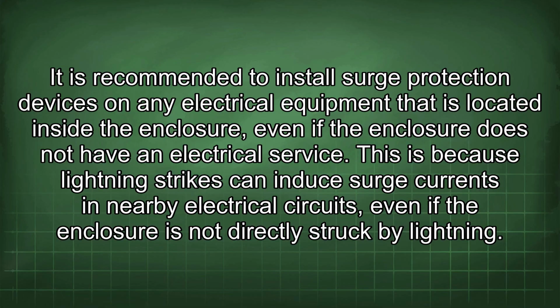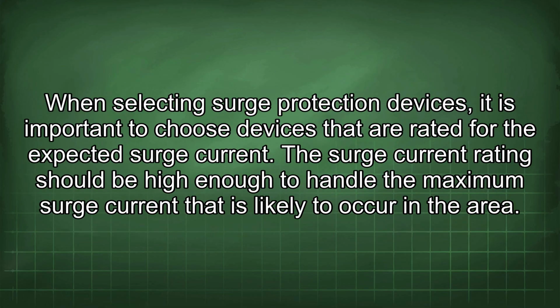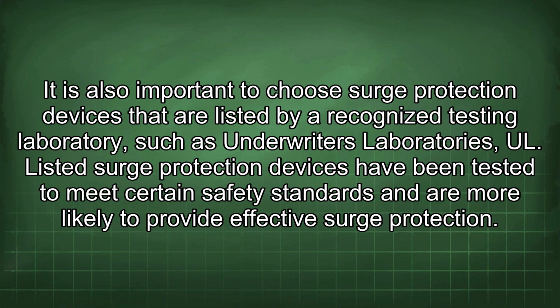This is because lightning strikes can induce surge currents in nearby electrical circuits, even if the enclosure is not directly struck by lightning. When selecting surge protection devices, it is important to choose devices that are rated for the expected surge current. The surge current rating should be high enough to handle the maximum surge current that is likely to occur in the area. It is also important to choose surge protection devices that are listed by a recognized testing laboratory, such as Underwriters Laboratories, UL.